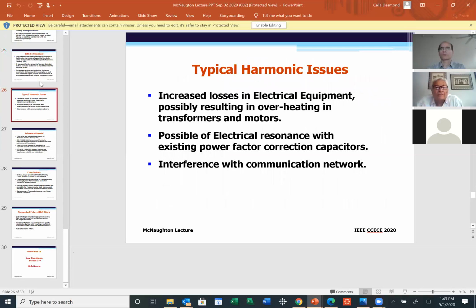Typical harmonic issues. Why are harmonics a headache? One of the key things is they increase losses in electrical equipment, possibly resulting in overheating in transformers and motors. That is one of the common problems with harmonics. If the equipment is improperly designed for harmonic applications or drive applications, then potentially you could experience overheating issues. The first time I experienced this problem was in 1983 when I was testing a drive with a 3000 horsepower load commutated inverter, where the motor overheated and we had to basically rebuild the motor.